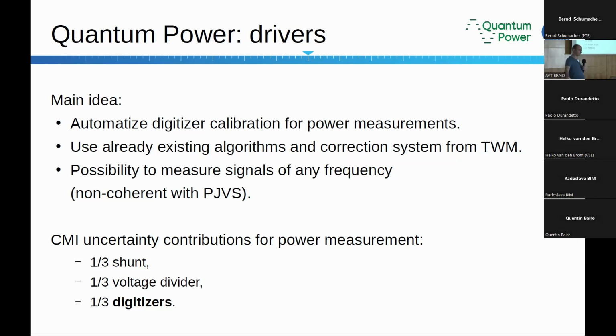and to simplify the measurements and everything. Because yes, all of you know how to calibrate the digitizer to, I don't know, ppm level or better, but how long does it take you to do it? You have to spend some time before the measurements, after the measurements to check it. And this system is about that all the digitizer calibration is made automatically using the Josephson. And of course, you can decrease the uncertainty because you are calibrating just before the actual measurement or after, and it's done automatically and so on.